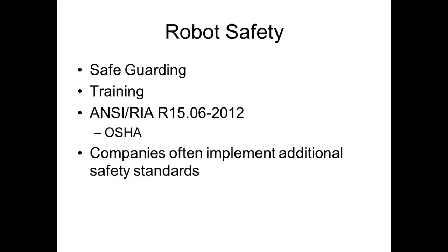They'd hit one of these stop buttons and the whole line would shut down. While they're trying to figure it out, everybody got a break. It took them a while to go around and find all these stop buttons, so we set up a big panel board that showed all the stop buttons, and when one was pressed, it kicked out on the panel.